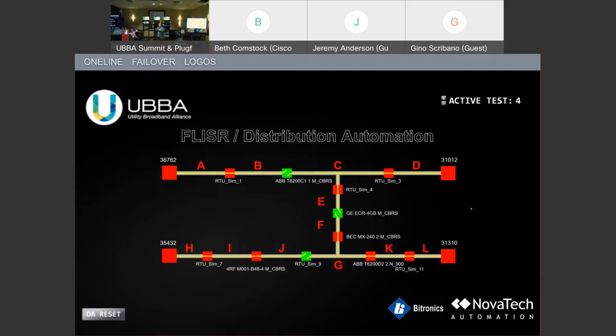We said, hey, we don't want to be out of power for hours and wait for somebody to go out there and manually do something about it. So we're automatically going to do something about it. And the most simplistic form of that is reclosing. And so reclosing is, hey, if I saw a fault and met a few certain categories, if it's a really hard, strong fault, i.e. not a cat or a tree, I'm probably just going to stay locked out. But if it's a transient fault, after a fault occurs, I'm going to wait some amount of time, i.e. your lights go out. It's usually 3 seconds. It's going to wait 3 seconds.